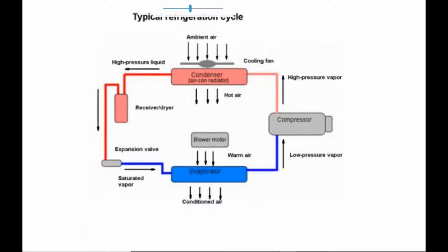So the high pressure vapor is hot, and it cools off. With the same combined gas laws, you'll be able to work out that it will condense, like you get condensation on a window, into a liquid. It's lost enough energy to condense into liquid. That's how they choose the fluid, the R134a. It turns to high pressure liquid. So this is all high pressure.